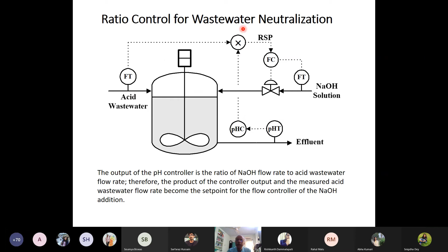In this case, ratio controllers do not require any kind of dynamics, any lead-lag element or so on. It's a pure gain element only. But in some cases, you also require dynamic compensation. For this example, let's say this is a multiple feed distillation column. Because of the flow rate of one of the feeds, the composition of the bottom stream will change. It may be a distillation column, or some absorption or separation column.